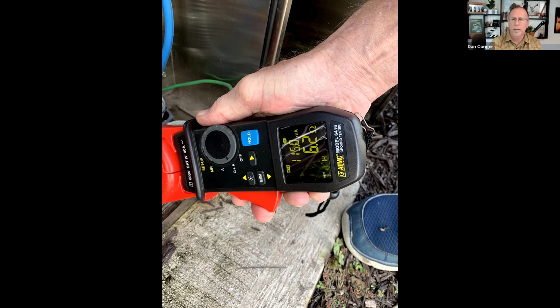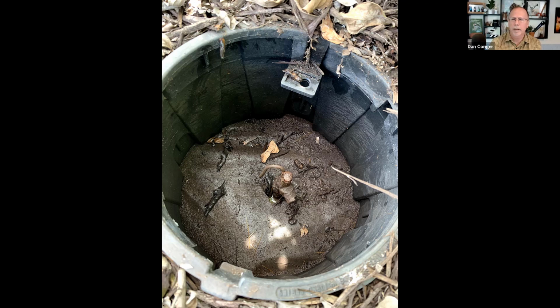Right. So here was the other end of that. This is a rod, and then there's a plate connected to that as well. So that's probably why there's two leads coming in. This is an inspection box, so you can see the ground rod and inspect it and make sure that it's properly connected, because if the wire that goes there is not connected firmly to that ground rod, it's not going to do any good.